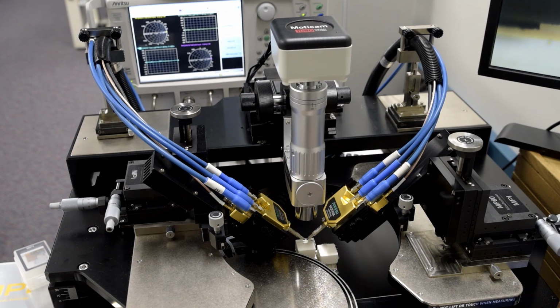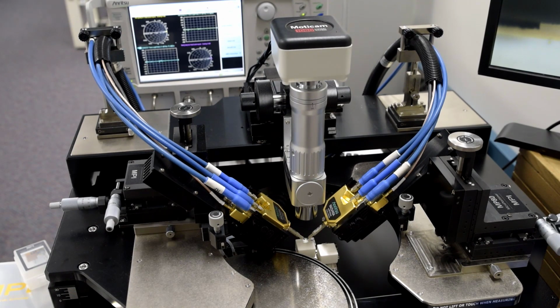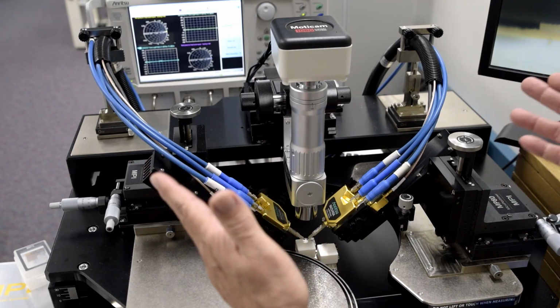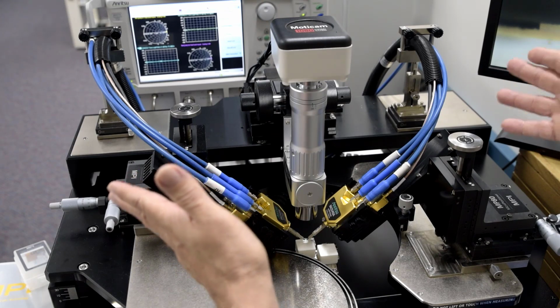So at this time, we could simply land our probes onto a through or a short and evaluate the probing stability over a period of time. And if that probing looks good and stable, then we could move on and perform our measurements. However, if some issues crop up, then we'll want to break down the system and isolate what that problem might be. So for instance, in this case, instead of landing on a through, we could remove the probes and connect shorts to the test ports, and then look at the system in this configuration and determine if there's any drift due to the system, the environment, etc.